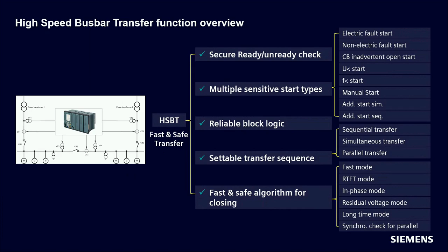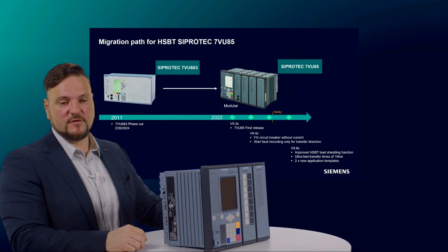So when we talk about the migration part of the HSBT function, we are coming from the SIPROTEC 4 device to a SIPROTEC 5 device. The SIPROTEC 4 device 7VU683 was released in 2011. And now with the 9.30, we released the 7VU85 based on SIPROTEC 5. So the SIPROTEC 4 device is already discontinued. The last order is in September 2024, and the new device is already available on the market.